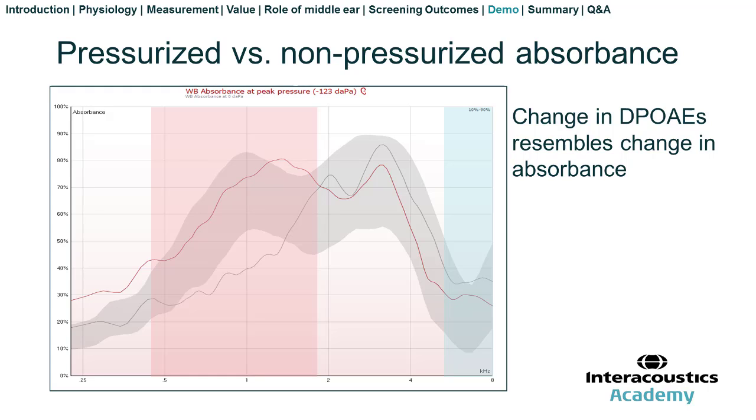So in other words, if you have a response that's near the top of the graph, or 100%, that just means that all of the signal that was presented to the ear has been absorbed by the tympanic membrane, middle ear, en route to the cochlea. However, if you have a response near the bottom, or at 0%, that just means that all of the signal that you presented to the ear has been reflected back into the microphone or the probe that's situated in the ear canal.